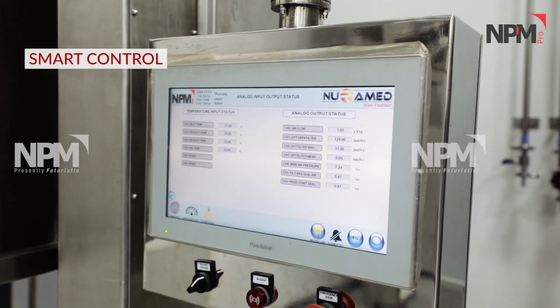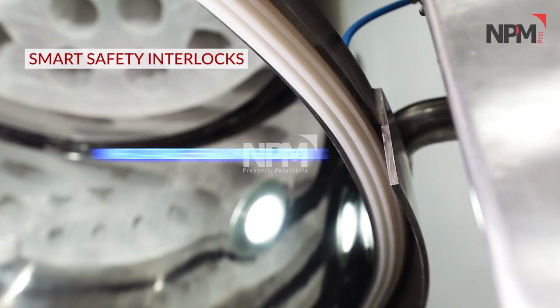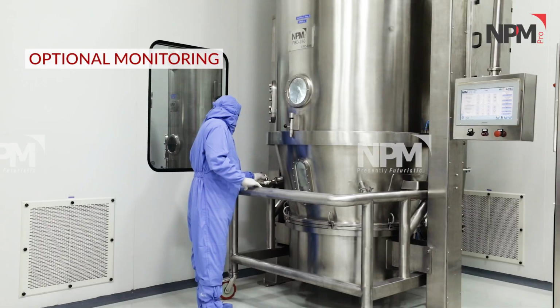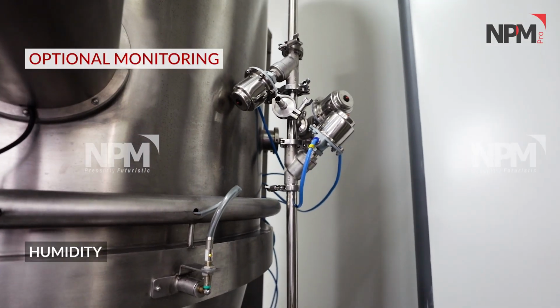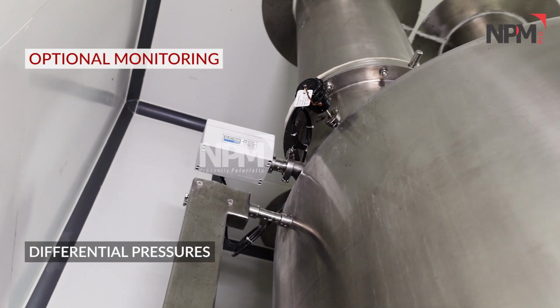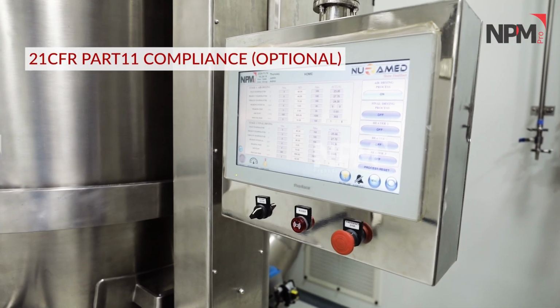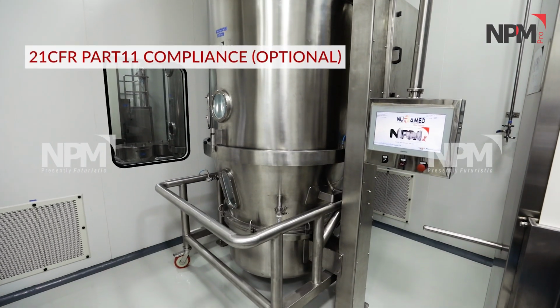Controlled via manual or PLC HMI panel, the FBD offers different alarms, interlocks, and optional monitoring of air velocity, humidity, particle flow and differential pressures. 21 CFR Part 11 compliance can be added if required.